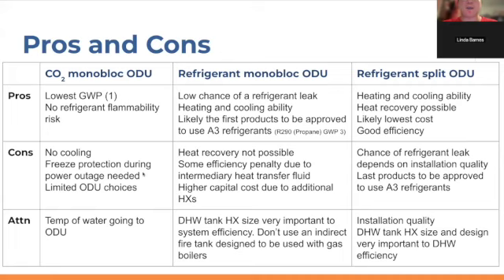Now, generally, refrigerant monoblock outdoor unit type combi heat pumps will have some higher capital cost due to those additional heat exchangers. Later, we'll talk about the water heater tank and other things, where there's also a pretty significant capital cost difference in order to have a domestic hot water tank paired with a refrigerant monoblock outdoor unit. We'll look at that some more. That last row, attention, is things that you need to pay attention to when you're working with a contractor to develop a combi system of this typology.